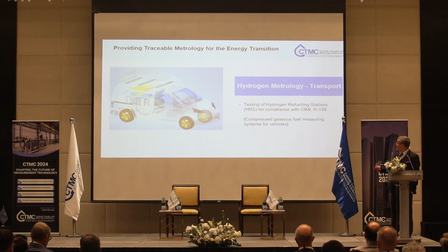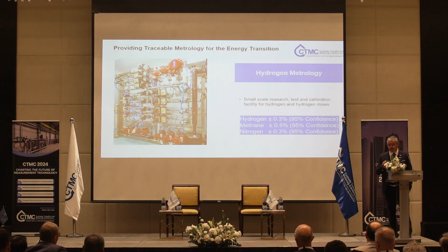We also have a small-scale research, test and calibration facility for hydrogen and hydrogen mixes. It's fully operational and available for hire, with some pretty low uncertainties. We use hydrogen, methane and nitrogen, again on purpose - we want fluids whose properties we understand in order to make the metrology as good as possible. We use methane as a substitute for natural gas because natural gas is maybe 95% methane, so it's close, but we understand the behaviour better.